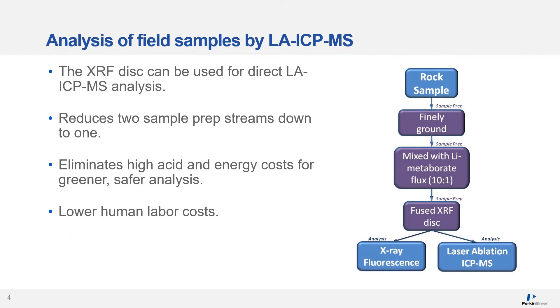An alternate approach to traditional sample analysis is the introduction of laser ablation ICP-MS. The laser ablation ICP-MS analysis protocol entirely removes the acid digestion process, thereby saving all reagent, energetic, regulatory, and labor costs involved. The X-ray disc that is being produced anyway is used in the laser for direct analysis, resulting in overall lower costs and positively enhancing the bottom line.